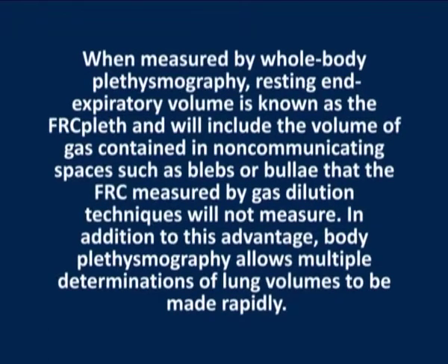When measured by whole body plethysmography, the resting end-expiratory volume is known as FRC pleth and will include the volume of gas contained in non-communicating spaces such as blebs or bullae that the FRC measured by gas dilution techniques will not measure. In addition to this advantage, body plethysmography allows multiple determinations of lung volumes to be made rapidly.